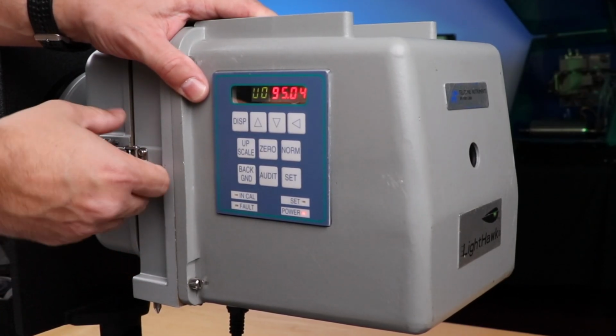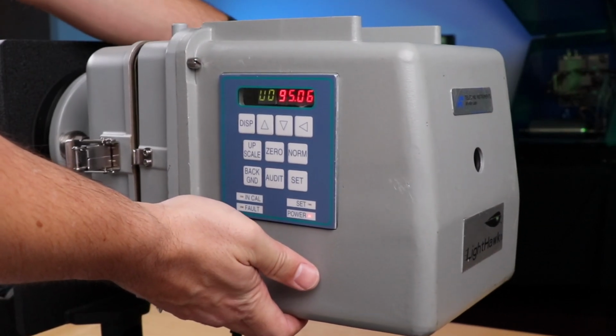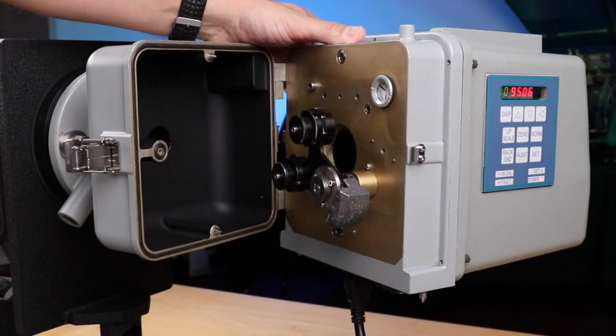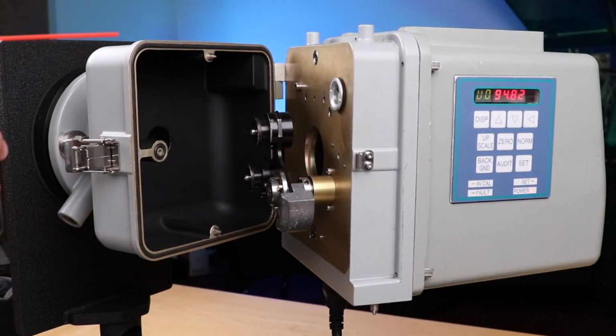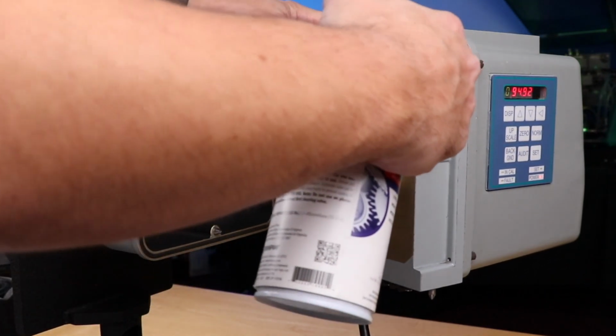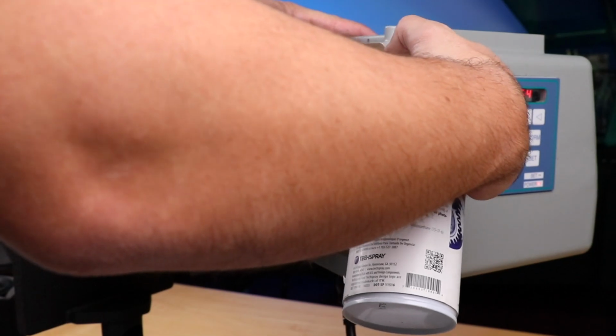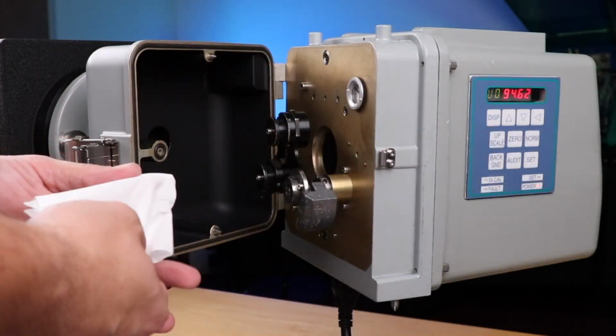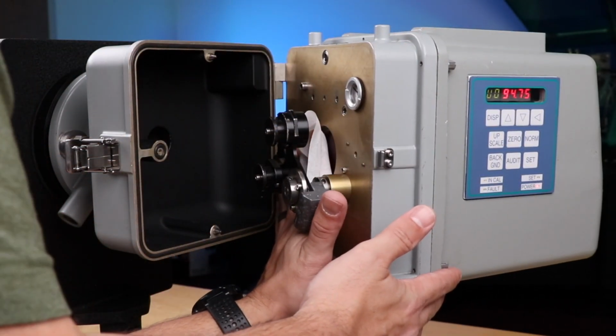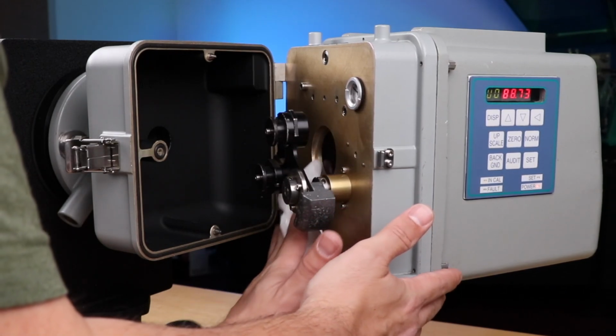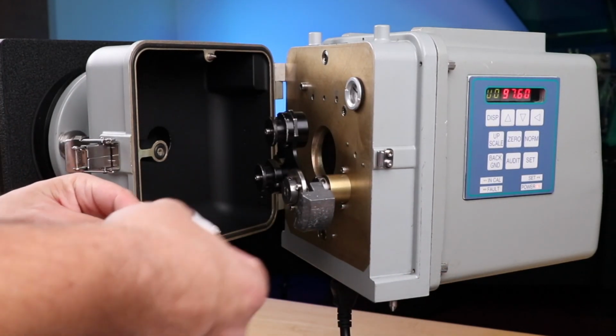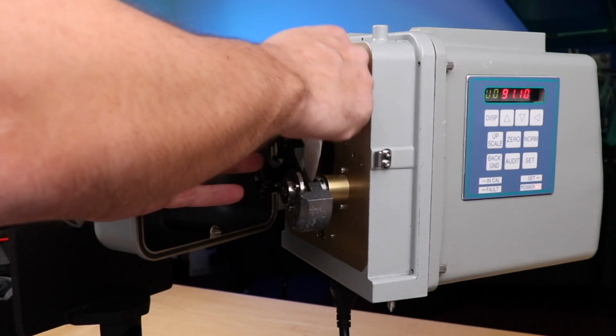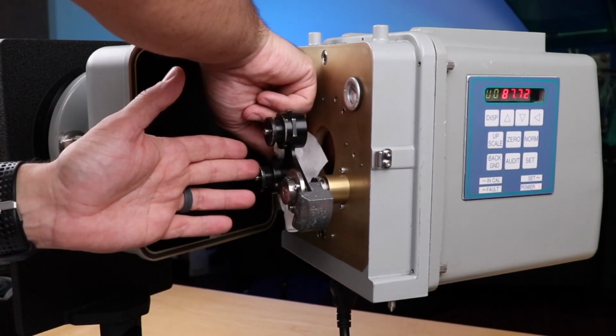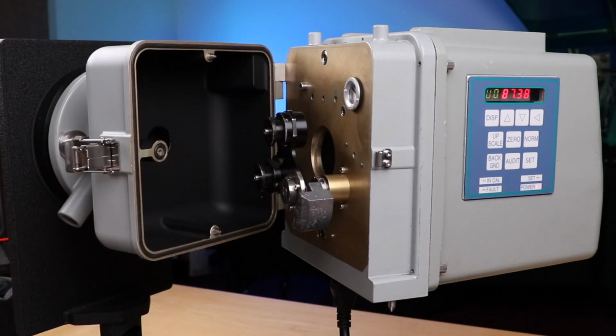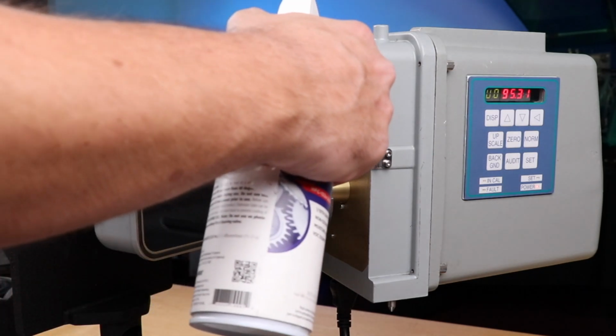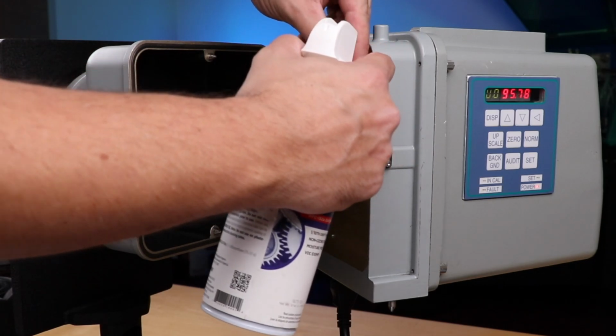First, change the blower filters. Then we can continue on to cleaning the optics. Open the optical head unit. Gently blow off the exit window and the cal fixture with air to remove any large dust particles that could scratch the glass during cleaning. Wipe the exit window and calibration mechanism optics with the 50/50 cleaning solution and a lint-free cloth. Blow off the glass once again to verify all moisture is evaporated.